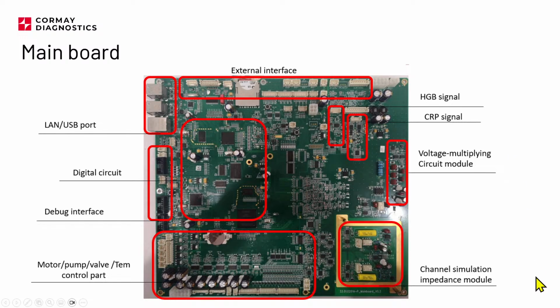So here we have the CPU board. On the top of the impedance channel preamplifier, there will also be a metal can, right? Because, as I said many times already, we are dealing with very low voltages, so we want to insulate this circuit from outside interference. So there will be a metal can. Here we have a section which is supplying power to the motors, pumps, valves. Stepper motor drivers are here also. So this is controlling the mechanical part of the analyzer.